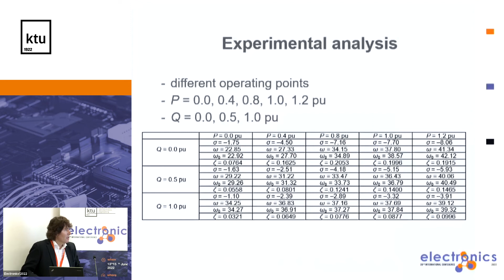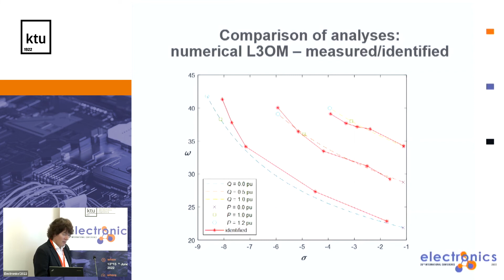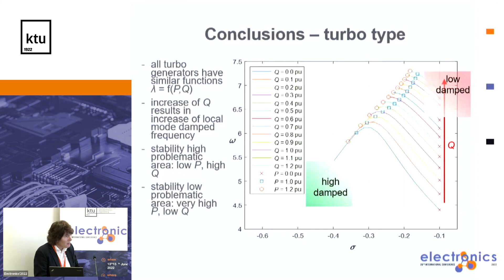We made this for different operating points, calculated eigenvalues, and drew them here. The blue dotted line means calculated from the mathematical third order model, and the red points mean the estimations of eigenvalues from measurements. We can see that our conclusions from a linearized model agree with the measurements on the real object. Just to remember, it was a turbo type generator, very fast, and we obtained similar dependencies.